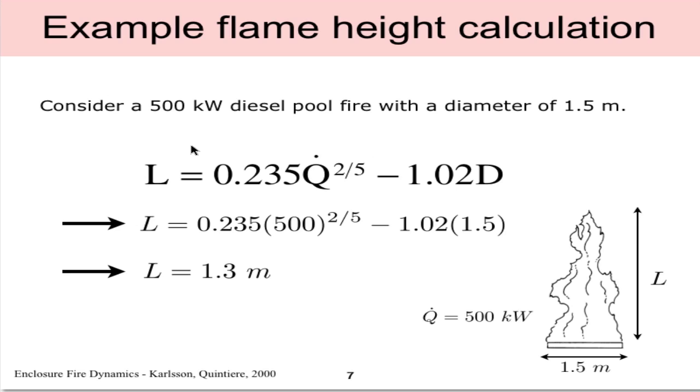Let's consider an example where we have a 500 kilowatt diesel pool fire with a diameter of 1.5 meters. If we have Q of 500 and a diameter of 1.5, if we plug those into the above equation and notice the units are consistent, 500 kilowatts, 1.5 meters, we get out a physical flame height L of 1.3 meters from this equation. So 1.3 meters is about a 4-foot flame height.